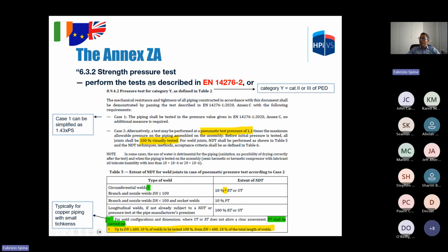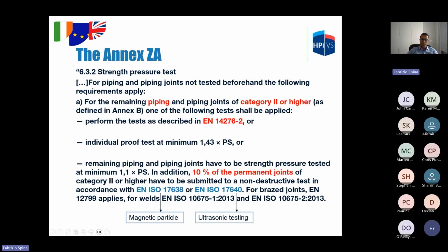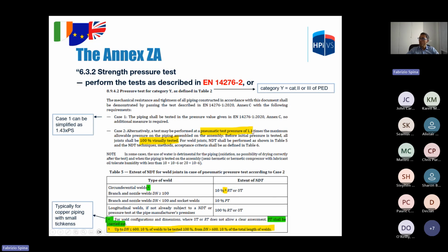In this slide, we can check option 1. This is a snapshot of EN 14276 part 2. Category Y piping is the same as category 2 or 3 of PED, and it foresees two cases. Case 1, which is the same as before, a pressure test at 1.43 PS. Case 2, which is similar to the third point in the previous slide, a pneumatic test at 1.1 PS, 100% visual inspection, and NDT.